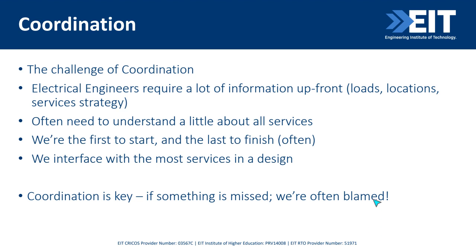Now, the challenge for us is not only do we need to make sure everything is coordinated, but we start doing that process at the beginning of a project. So at the very start, when we're trying to size our infrastructure, we need to know electrical loads. So to do that, we need to ask for that information up front, which can be hard because mechanical might not have made their selections yet. So we're asking for what their loads might be and where their equipment's going and how they're reticulating things around the building.